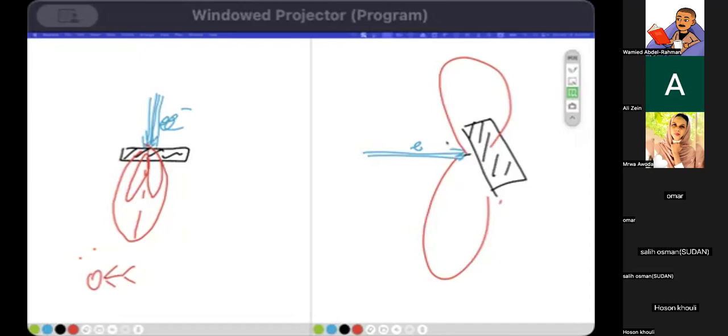TMRs, some people like to scan TMRs. I don't suggest you do TMRs. Just a PDD is enough. You can scan PDD, you scan profiles, and profiles you scan at Dmax and at 10 centimeters. Okay, so it is as if you're doing an annual check, a beam scanning check on the beam.